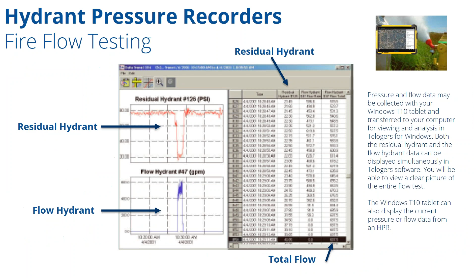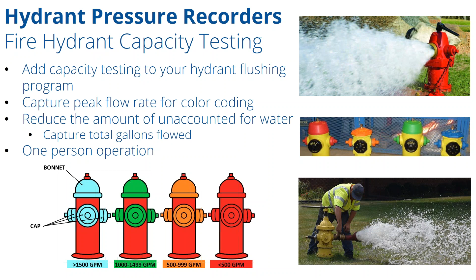During your flow test and any flushing activities, we have the ability to do fire hydrant capacity testing. All the water utility folks attending today are familiar with the color of a hydrant bonnet and cap. These actually signify real world gallons per minute flows coming out of the hydrant. With our hydrant pressure recorder, we're able to capture the peak flow rate so you can apply the proper color coding onto your fire hydrant caps and bonnets.